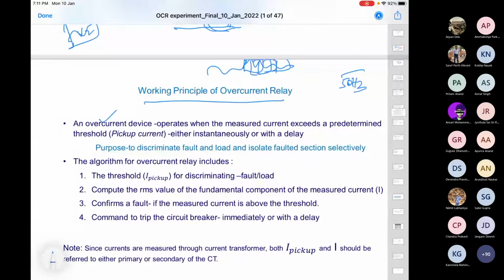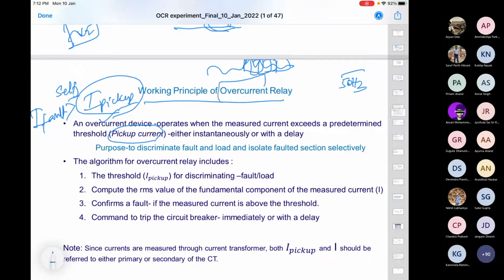So we know an overcurrent device, by this background, operates when the measured current exceeds a predetermined threshold. We call it the pickup current. Pickup current means the minimum current above which the relay should operate. So pickup current is a setting current, a selection current. When the fault current is greater than this pickup current, the relay should operate. That is the first step of the principle we are talking about.